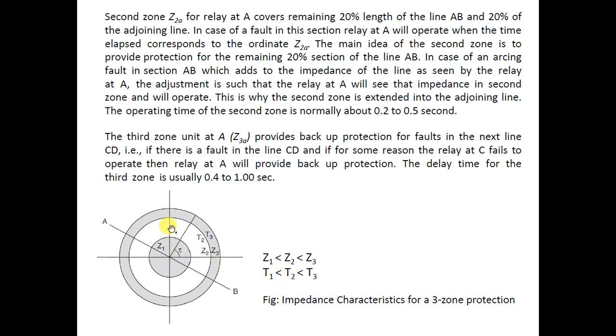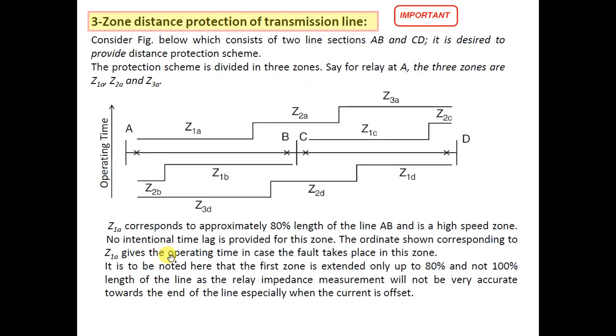If Z2 fails, the third layer of protection provided by Z3, which covers a greater radius, will come into action. Z1 is less than Z2, which is less than Z3. More coverage is provided by Z3, but the operating time is also the highest for that element. So if the primary layer fails, the secondary layer will come into action in a greater operating time; if the secondary fails, the third layer will clear the fault within the highest permissible time T3. This concept is utilized in three-zone distance protection.